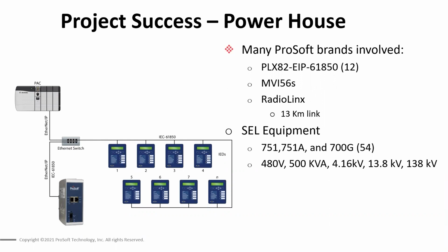And last two questions. Thanks for hanging in there, everybody. Is there any way to put the new modules in redundant PLC racks? Yes, the new modules will reside in a redundant architecture, but as you know, this module still looks like an IO module, 225 IO connections, and so it must go in the remote rack. The only thing that can go in the PLC racks is the processor and all that stuff.